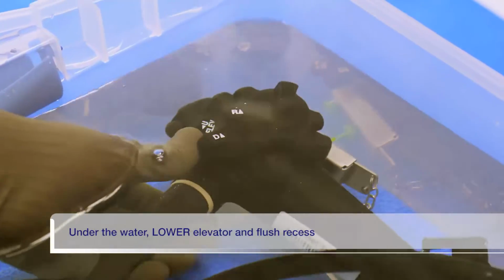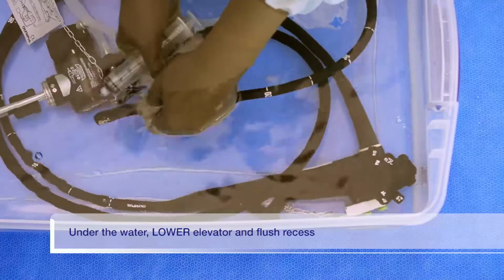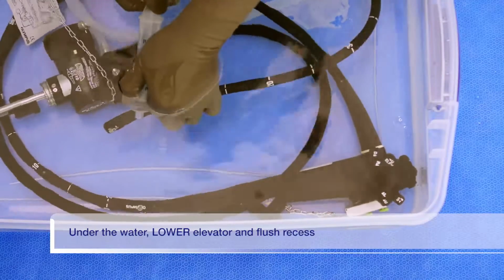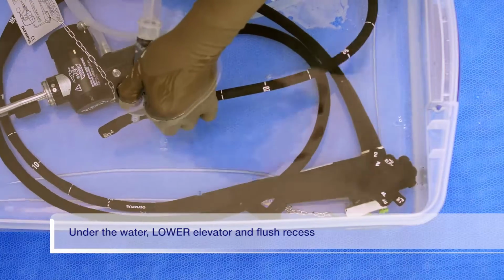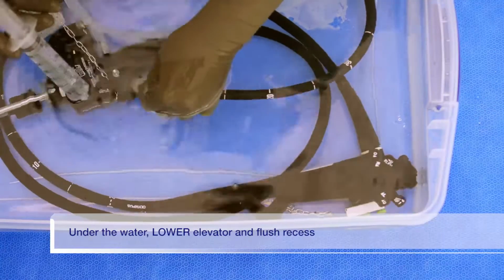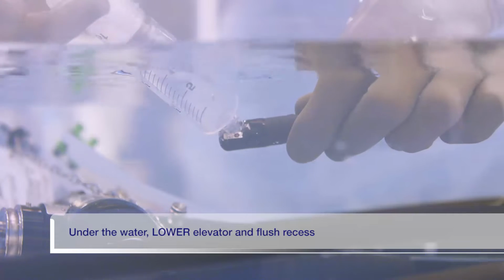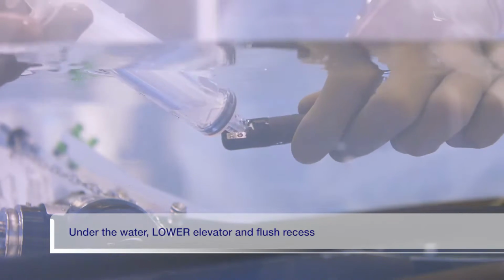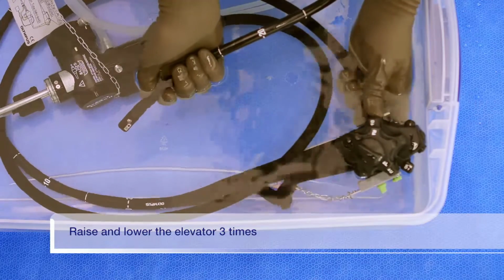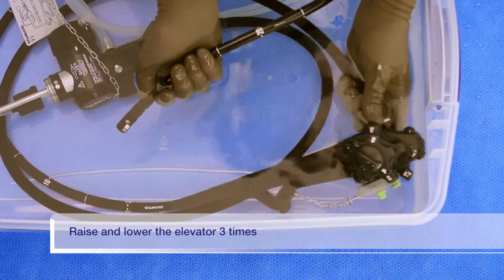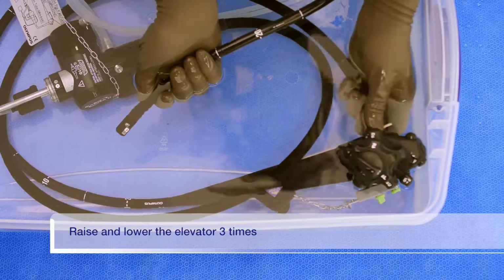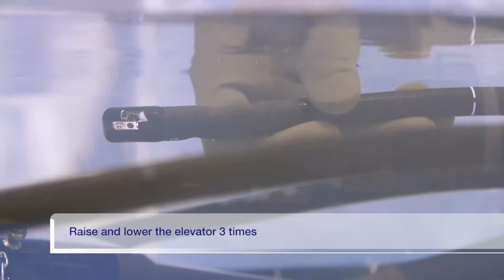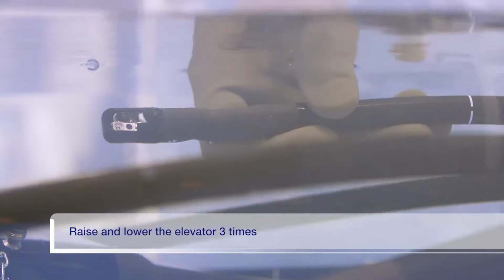Lower the elevator and insert the tip of the 30 milliliter syringe into the interior of the forceps elevator recess in the rinse water. Then flush the interior of the recess with 30 milliliters of the rinse water. Turn the elevator control lever to raise and lower the forceps elevator 3 times, keeping the distal end of the endoscope immersed in the rinse water.